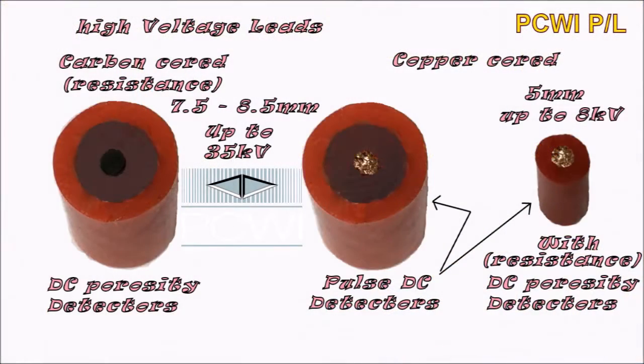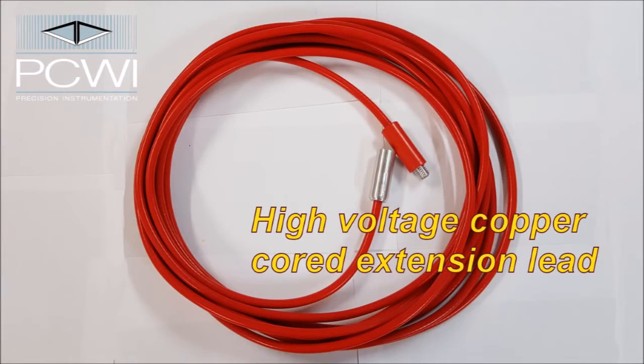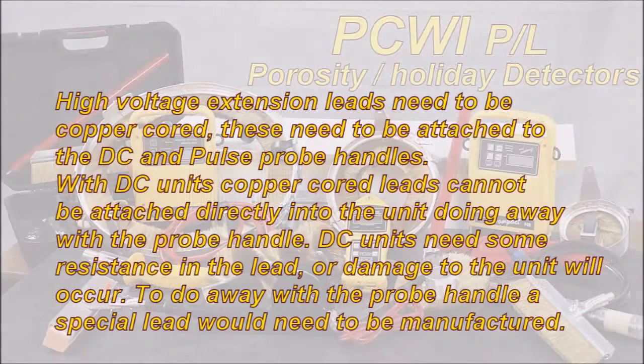High voltage leads: carbon cored resistance leads, 7.5mm to 8.5mm in diameter, up to 35kV, mainly for DC porosity detectors. Copper cored is used with pulse DC detectors. You can get a much reduced 5mm lead that can go up to 8kV.